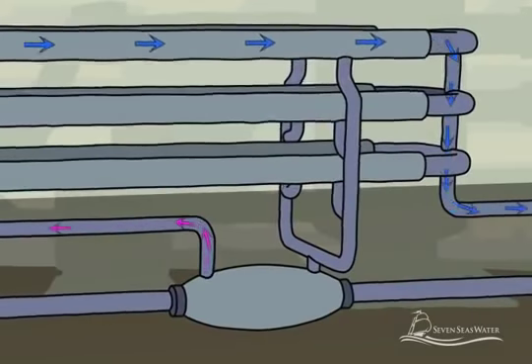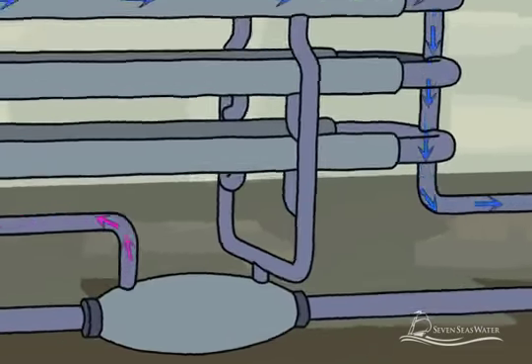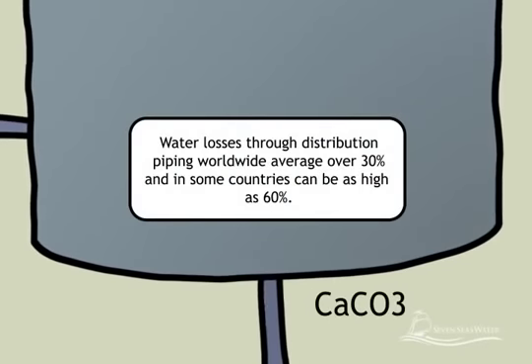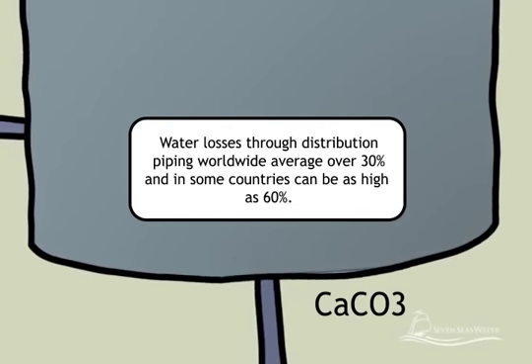Approximately 40% of the seawater that enters the system is converted to potable water during the reverse osmosis process. The potable water is further treated by adding calcium carbonate to improve the taste and bring the pH to the neutral range.